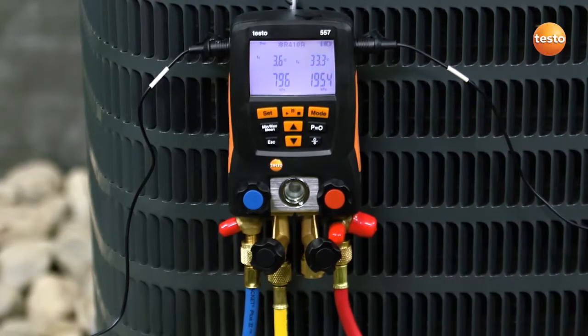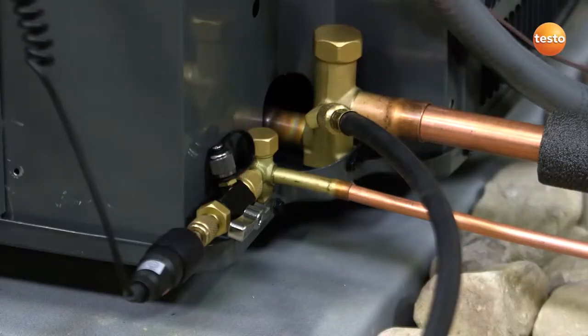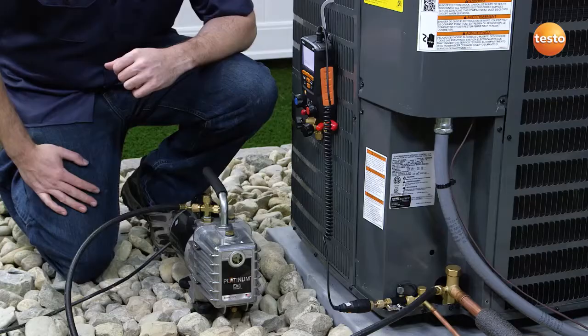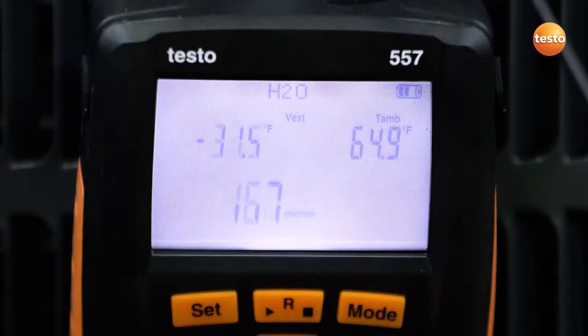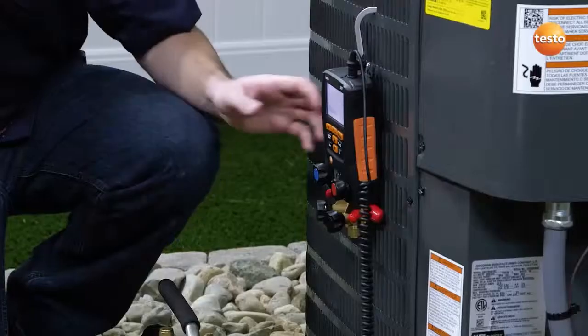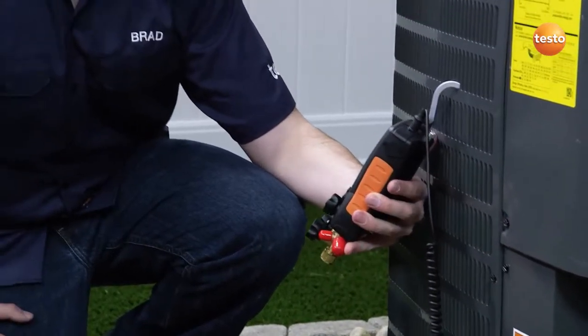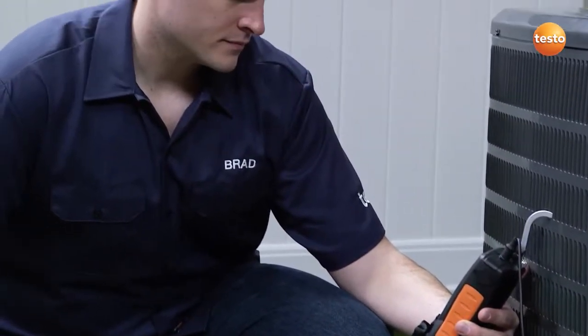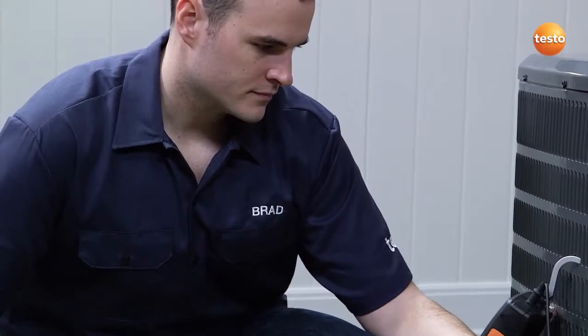and subcool measurements. The external vacuum probe can be directly connected to the system, eliminating the need for pulling vacuum through hoses and manifold valves, providing faster and more reliable evacuations. Automatic heat pump mode detects pressure changes and automatically adjusts to display the correct superheat and subcool measurements.